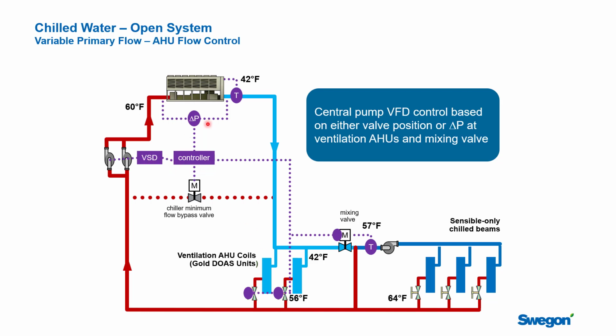Now, this system is a variable primary flow system, so they're going to be monitoring the flow or the pressure drop across the chillers to maintain minimum evaporator flow rate. And at some point, that would open up the bypass here so that we would maintain a minimum flow in this loop through the evaporator as a way to avoid going laminar in the heat exchangers and causing chiller issues. If this is a primary-secondary plant, you wouldn't be having this. You would have a bypass, but you wouldn't have this level of control. This part in here is all specific to whether you're primary-secondary or variable primary flow, which is what's shown here.